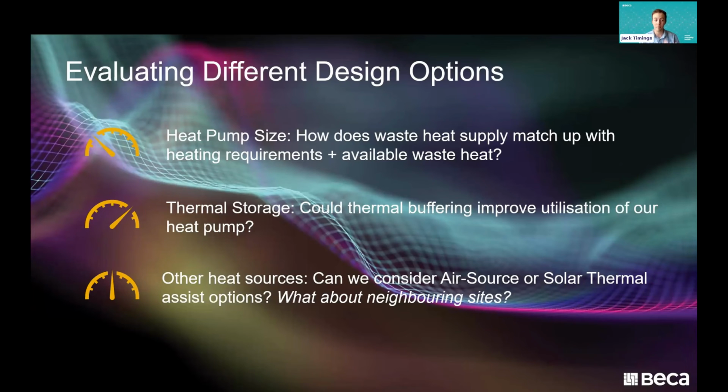We investigated partnering with a number of neighbouring sites going forward when they had asset replacements coming up, so accessing waste heat from beyond the site boundaries. None of those opportunities lined up during the stage 1 project implementation scope. But we've talked to them about a couple of asset refresh opportunities in the next 5 years, which look really promising. But we did end up installing some solar thermal generation to work in tandem with our refrigeration plant's heat rejection to increase the role that our heat pump could play.